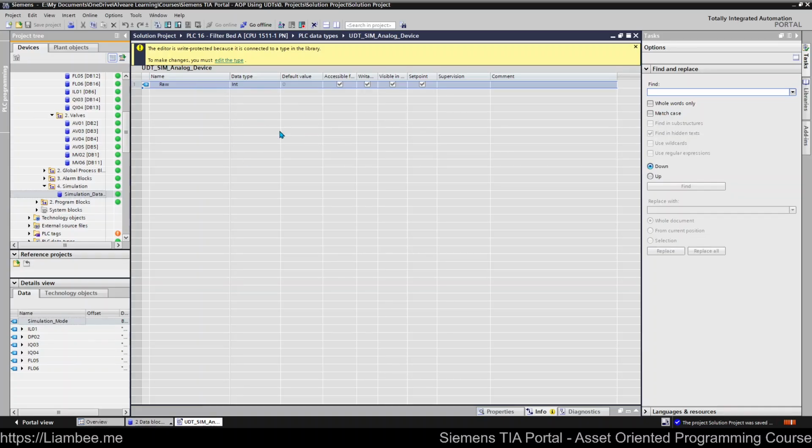Putting things in their own UDT means, just like the real data, you can't mix simulation data by accident on any interface because it's expecting a particular type. It keeps things in that hierarchy approach of this UDT only works with an asset of this type.